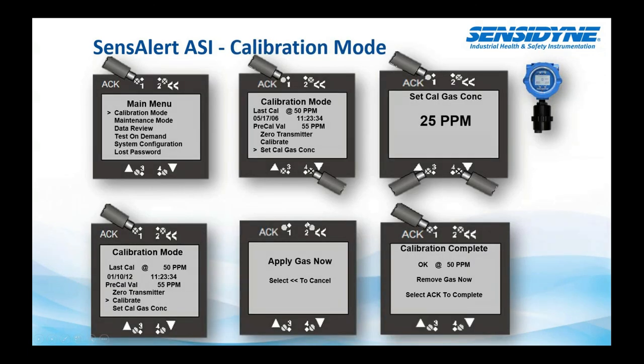Real simple when it comes to doing calibrations. This is the complete calibration process for doing a calibration with the SensAlert ASI. Everything is in plain English. You enter the main menu mode, and you'll see right there you've got your calibration mode, your maintenance mode, data review, and so on. To do a calibration, we would acknowledge your calibration mode. It'll display your last calibration as well as the three previous calibrations. So you actually can display four historical calibrations with this unit right in the transmitter. And all that data is actually stored on the sensor. So the transmitter is just reading the sensor.